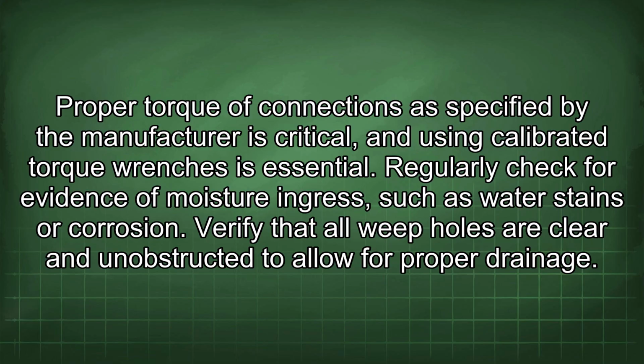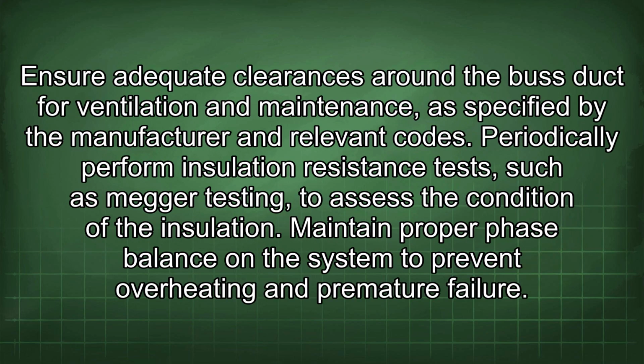Regularly check for evidence of moisture ingress, such as water stains or corrosion. Verify that all weep holes are clear and unobstructed to allow for proper drainage. Ensure adequate clearances around the bus duct for ventilation and maintenance, as specified by the manufacturer and relevant codes. Periodically perform insulation resistance tests, such as megger testing, to assess the condition of the insulation. Maintain proper phase balance on the system to prevent overheating and premature failure.